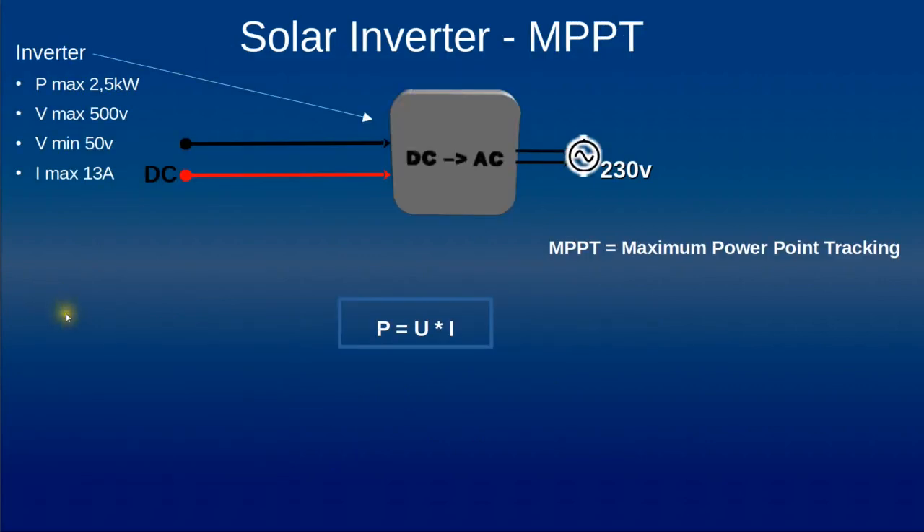Now we address the characteristics of the inverter. Here we have a system able to manage 2.5 kilowatts on the input side, which is acceptable since our panels provide a maximum of about 2.3 kilowatts. The maximum input voltage is 500 volts — acceptable — with a minimum voltage of 50 volts, which is when the system starts to convert DC to AC. The maximum input current is 13 amps, and since our short circuit current is only 11 amps, that is acceptable.